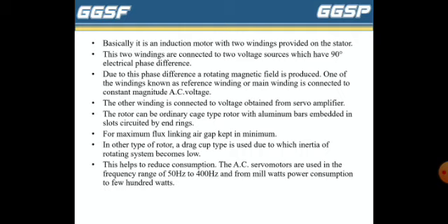The rotor can be an ordinary cage rotor type with aluminum bars embedded in the slots and short circuited by the end rings, with the air gap kept at a minimum for maximum flux linking. In another type of rotor, a drag cup type is used, due to which the inertia of the rotating system becomes low. This helps to reduce power consumption. The AC servo motors are used in the frequency range of 50 Hz to 400 Hz and from milliwatt power consumption to a few hundred watts.